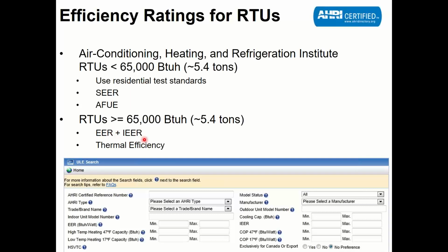Part load is significantly more important because full load only happens on the hottest day of the year, which is 0.4% of the time. Unless I've oversized it, then it's never. So IEER is more important. It used to be that we only had EER for commercial stuff, and then maybe like, I don't know, 8 or 10 years ago, we added IEER. And now we almost ignore EER, and we're almost fully focused on IEER, and I'll explain that too.